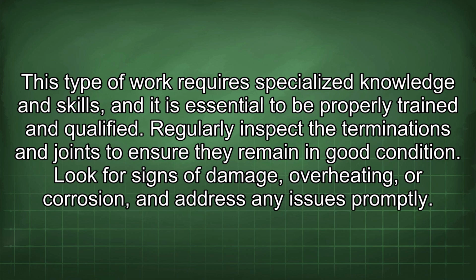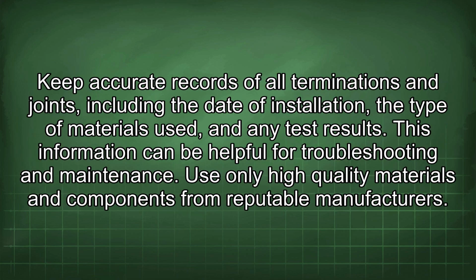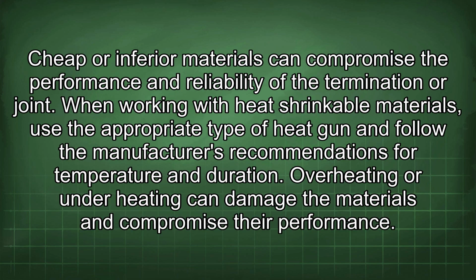Regularly inspect the terminations and joints to ensure they remain in good condition. Look for signs of damage, overheating, or corrosion, and address any issues promptly. Keep accurate records of all terminations and joints, including the date of installation, the type of materials used, and any test results. This information can be helpful for troubleshooting and maintenance. Use only high-quality materials and components from reputable manufacturers. Cheap or inferior materials can compromise the performance and reliability of the termination or joint.